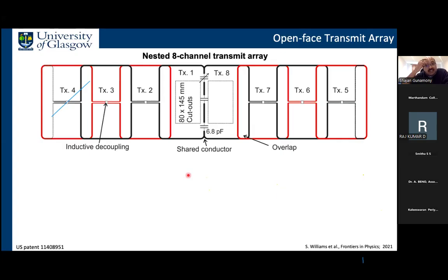Long story short, this is the 2D layout of the 8-channel transmitter array which I developed. We call it the nested 8-channel transmitter array. It has 8 conventional loops, shown in red and black, and all the adjacent channels are critically overlapped to cancel the coupling. And there's a nested arrangement of loops to decouple the next neighboring channels using transformer inductors.